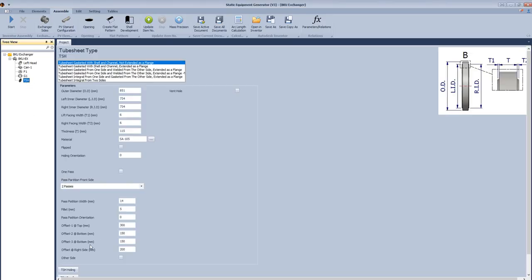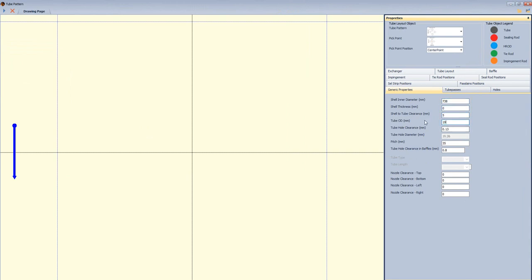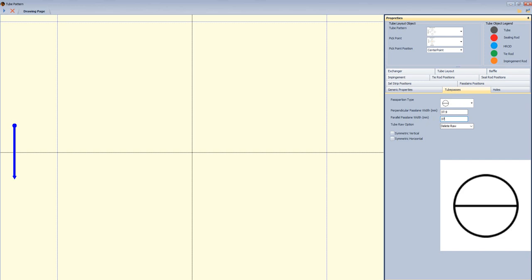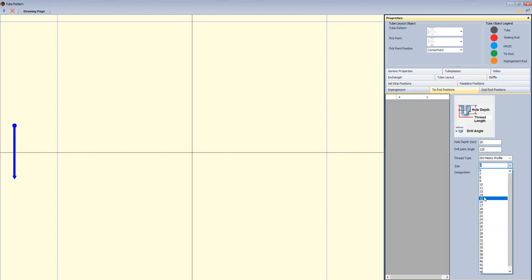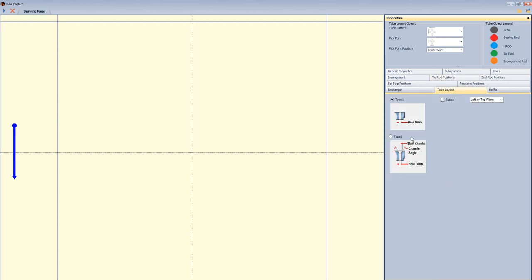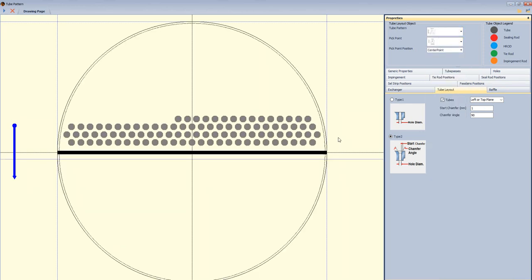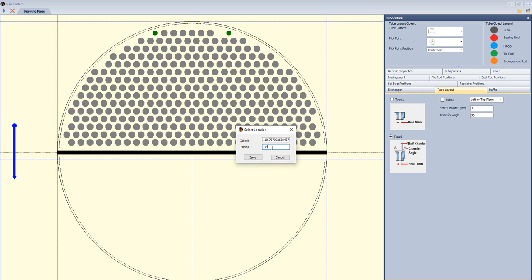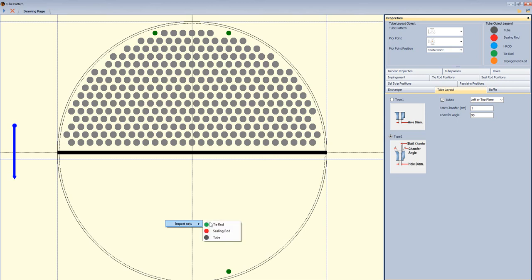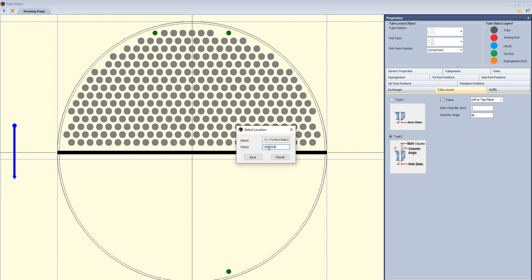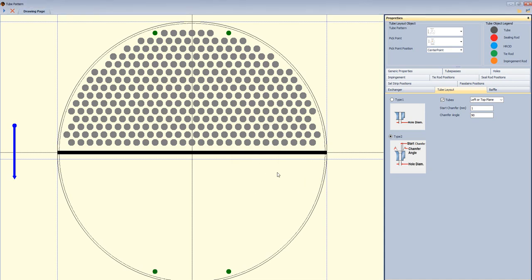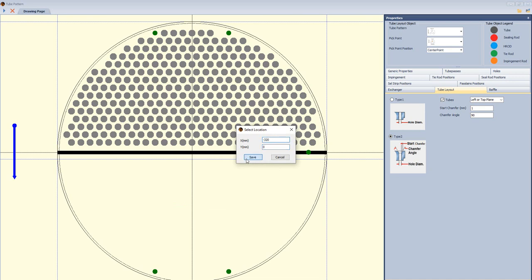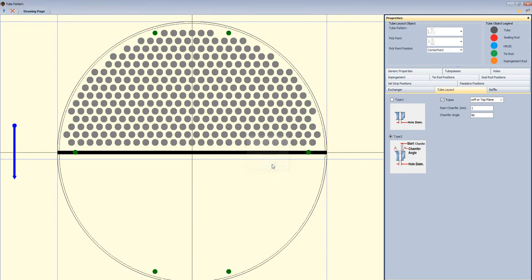After creating that, we will add the hole pattern. From here, we will define the dimensions of the tube pattern like inside diameter, tube outside diameter, and tube clearance. Select number of pass partitions, and the vertical and horizontal passing. Define the tie rod diameter. Select the hole definition of the tube sheet for the tube, then select the tube pattern. Now we have the tube pattern. We will remove a tube and convert it to a tie rod, and another tie rod at the bottom of the same location. Click save. Let's add another tie rod — define the location in Y and X. Let's add another two passes on the pass partition. Define Y to be at zero and X to be 320 with negative and positive values to add tie rod. Now we saved the information.